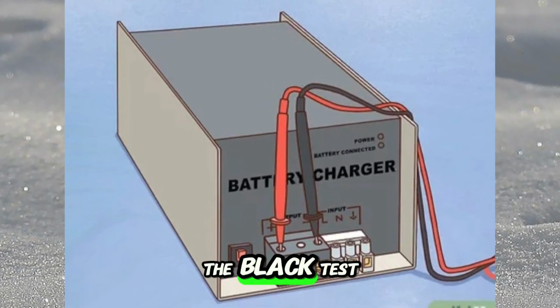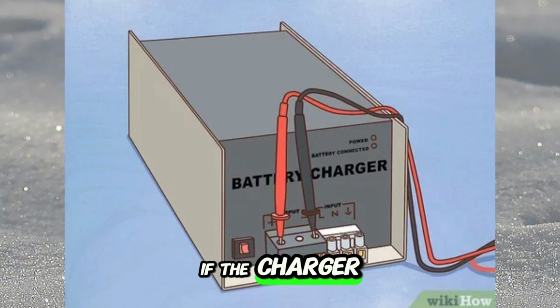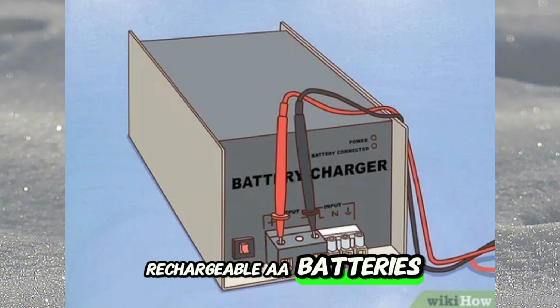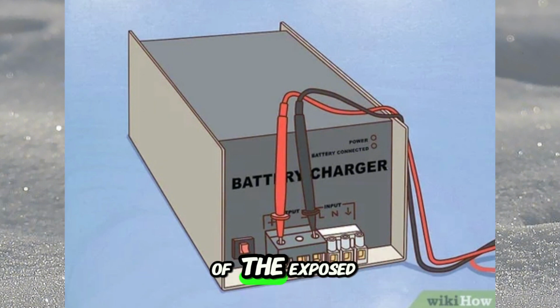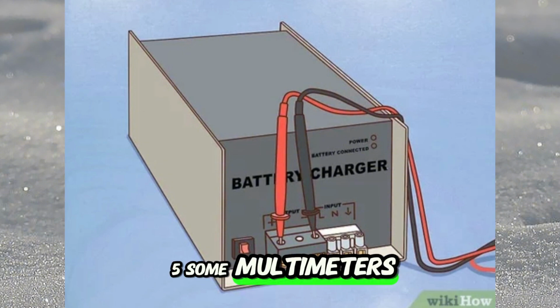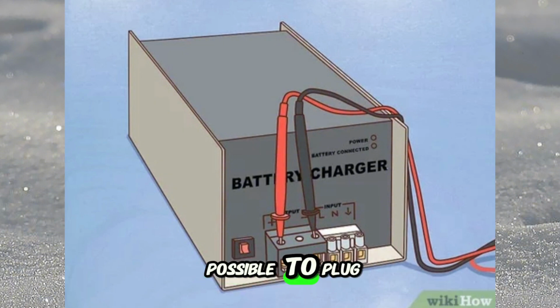Fourth step: touch the black test probe to the negative contact point on the charger. If the charger you're testing hooks up to a battery via a power supply cord, press the tip of the probe against the side of the metal prong at the end of the jack. If you're testing a receptacle charger like the kind used to reload rechargeable AA batteries, hold the probe to a section of the exposed metal on the side of the charging chamber marked -. Some multimeters have input ports that make it possible to plug certain types of power supply jacks directly into the tool.